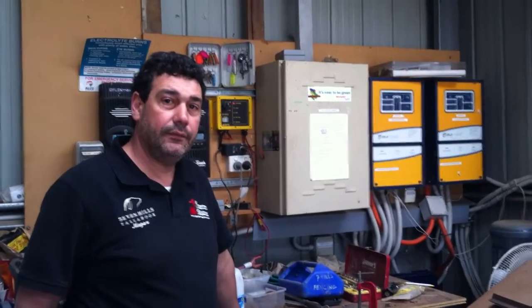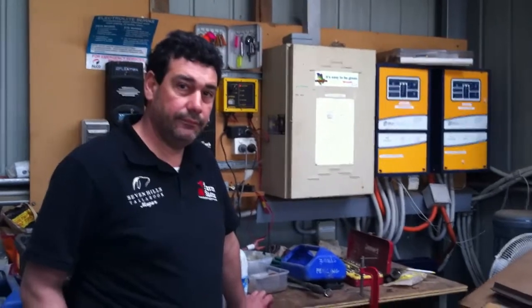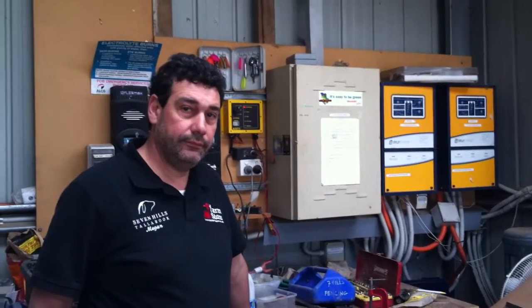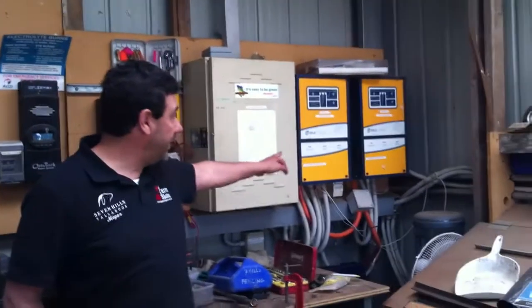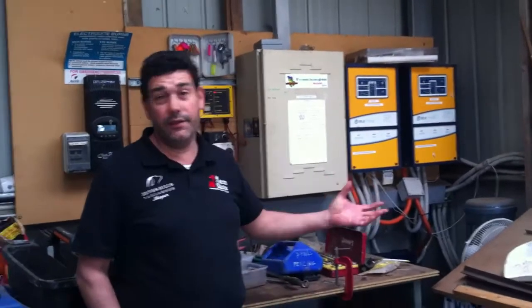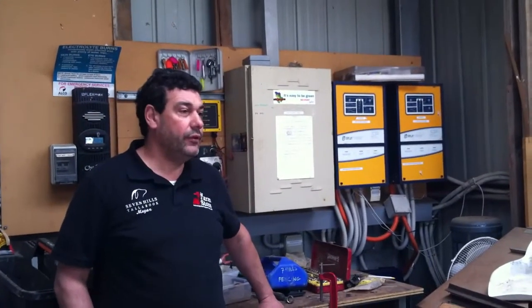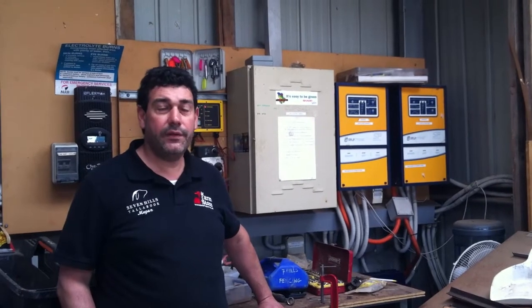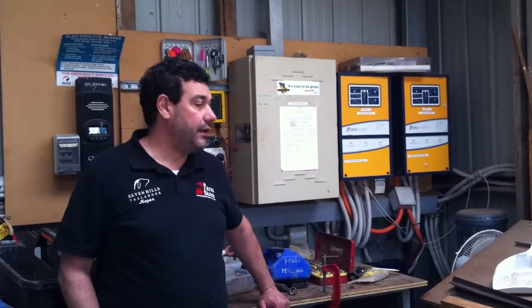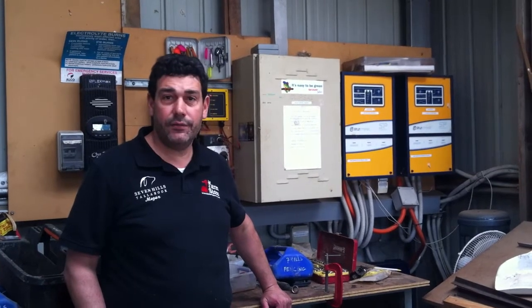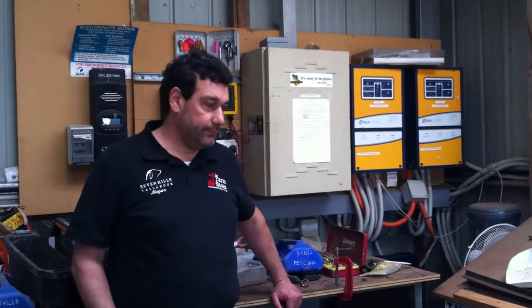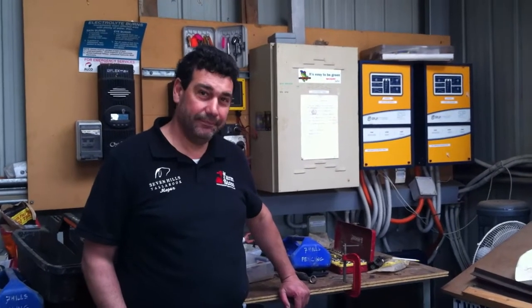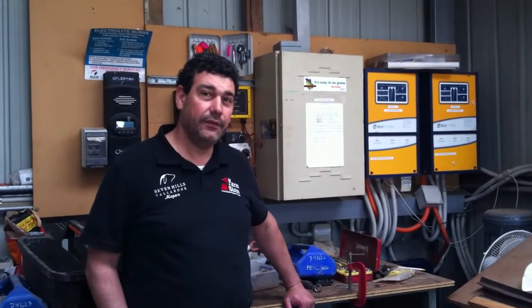So you have to check and keep them topped up. There's maintenance involved, but because of the usage they get, there's not a lot of time where they're not being cycled. When you're putting 125 amp hours into it quickly over a short period, you can hear them bubble and boil. We check them once a month, but top them up with water roughly every 3 months - about 30 litres across the 24 cells, so roughly 10 litres a month. Otherwise the plates inside get exposed and you lose capacity.